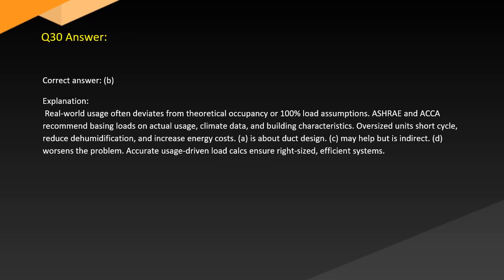Answer. Correct answer: B. Explanation. Real-world usage often deviates from theoretical occupancy or 100% load assumptions. ASHRAE and ACCA recommend basing loads on actual usage, climate data, and building characteristics. Oversized units short cycle, reduce dehumidification, and increase energy costs. A is about duct design. C may help but is indirect. D worsens the problem. Accurate, usage-driven load calculations ensure right-sized, efficient systems.